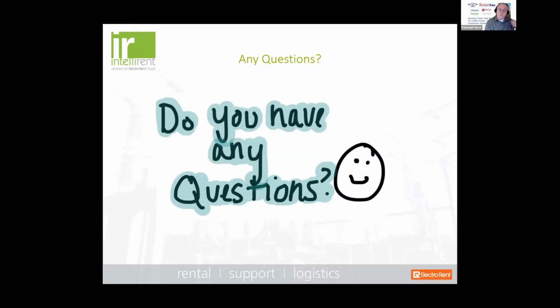In the last presentation, Fouad mentioned that CIGRE identified 40 to 50% of transformer failures were the result of tap changer failures. But I asked him why that was. Is there a good answer for that? Oh, absolutely. Why do they fail so high? Why are there so many failures? Absolutely. Well, first of all, you have to understand it's the only moving part in the transformer. That's why it's subjected to mechanical failure.